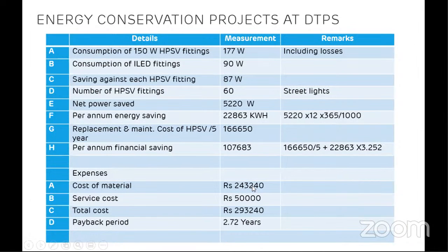The cost of material was 2,43,000 and the installation or service cost was 50,000 rupees. So the total cost came to roughly 3 lakh rupees. We have a per annum saving of 1 lakh rupees and a total cost of 3 lakh rupees, so our payback period comes to roughly 2.7 to 3 years. So you can see, by making such a huge investment of 3 lakh rupees, we get its payback in only 3 years, and in the rest of the years, this 1 lakh rupees per annum will be our benefit. So here you can see how making costlier investments will give you higher benefits in future in terms of energy efficiency.